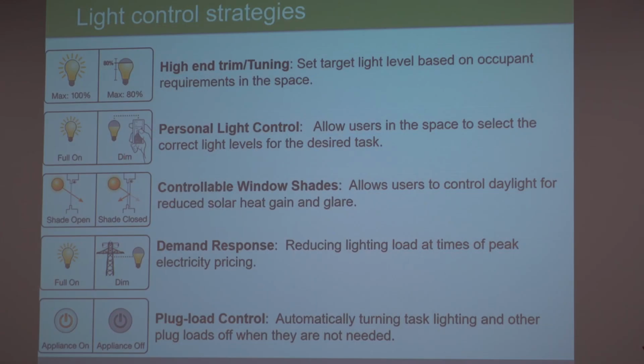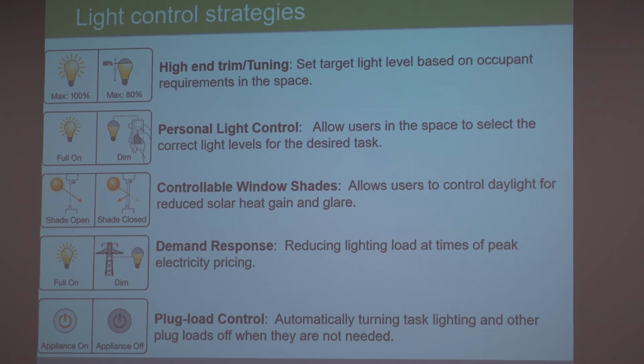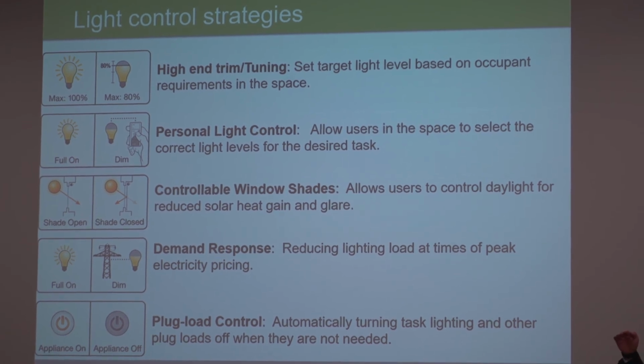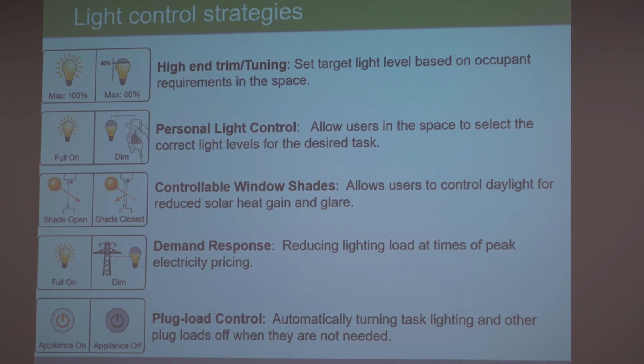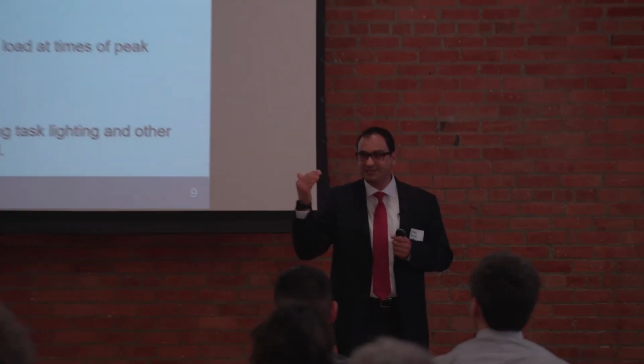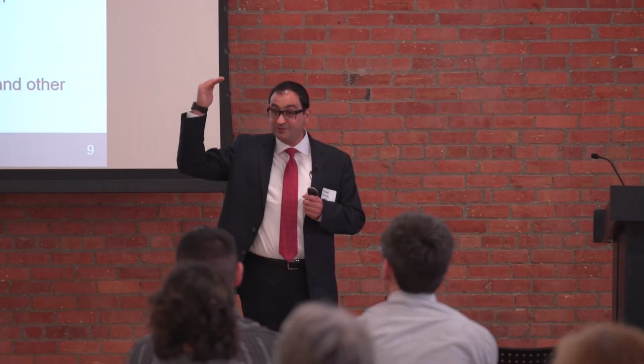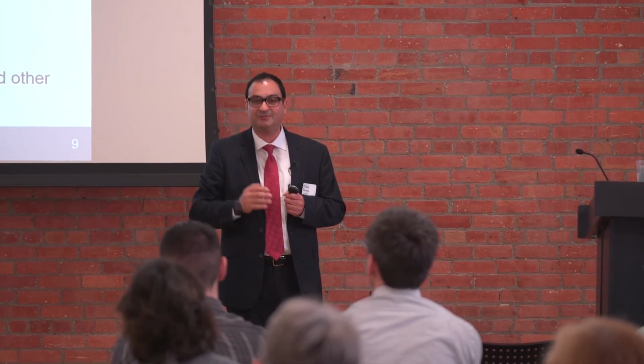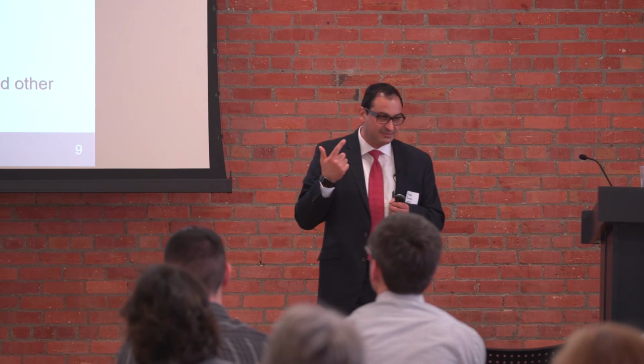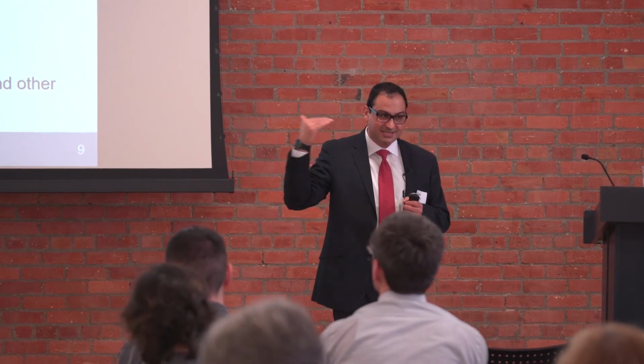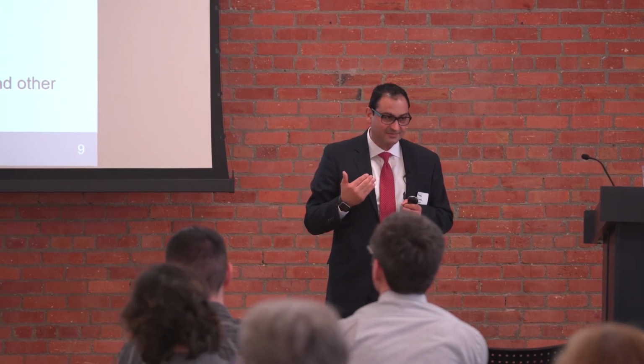Some more advanced light control strategies. There's high-end trim or tuning, and this is where you set a maximum light level in the space lower than the true full-on light level. The nice thing about this strategy is that the first 25% of lights, going from true 100% down by 25%, isn't even detectable by the human eye, yet you save about 25% in energy.